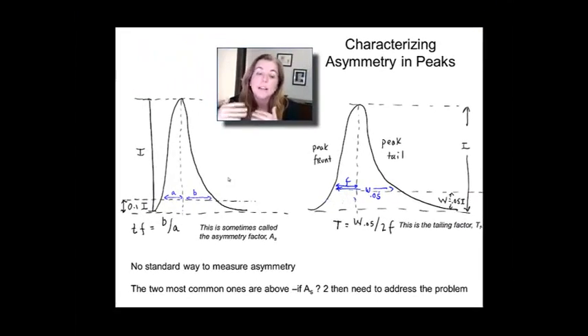Asymmetry factor might be slightly more common, but they give you a way of saying, okay, it's kind of bad or it's really, really bad. And generally, if you have asymmetry factors that are in excess of 2, you really can't use the separation. Something is fundamentally wrong with what you're doing, and you need to address the asymmetry in your peaks before you do any, certainly, quantitative analysis, and possibly even qualitative.